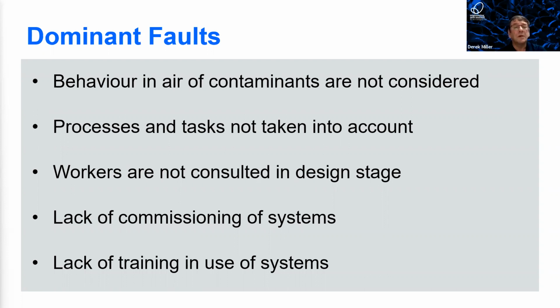So we spent about a morning playing around and eventually got it on a configuration that would work. Got it up and running, retested the whole system, and this time we went down to less than 1% of the workplace exposure standard. So we've gone from 10 times above to less than 1% of the standard, which meant it's now under control. So the system was fine, but the workers had never known how to use it.